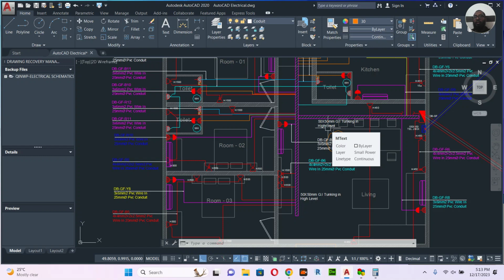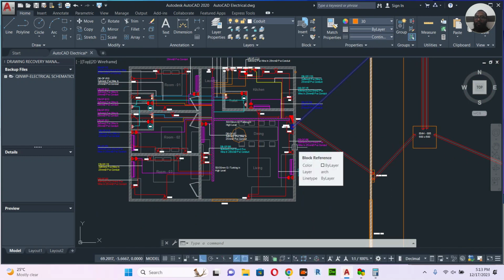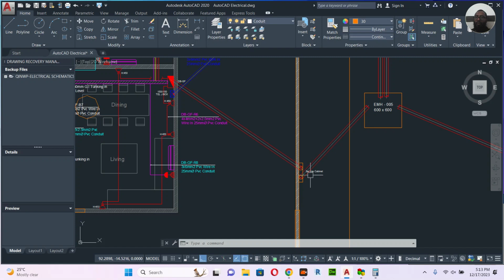Otherwise, you have to go to any catalog in your country to select the cable. That is the first thing. The second thing, as per that load, you will make an application form to the government: I need this much power. This is a different thing. If this is a big building, it's one project, so it will go to the SMDB. Here you have a service cabinet, through which the owner of the full compound will be charged. It will have one meter and one breaker.